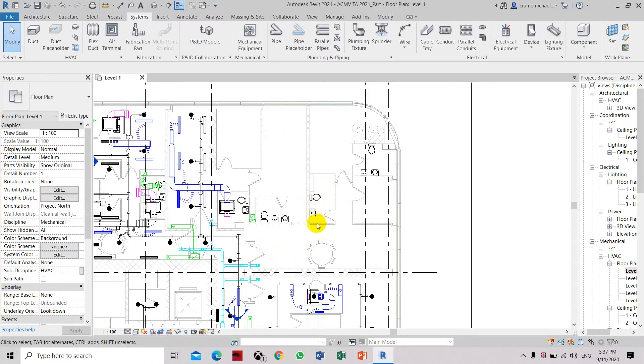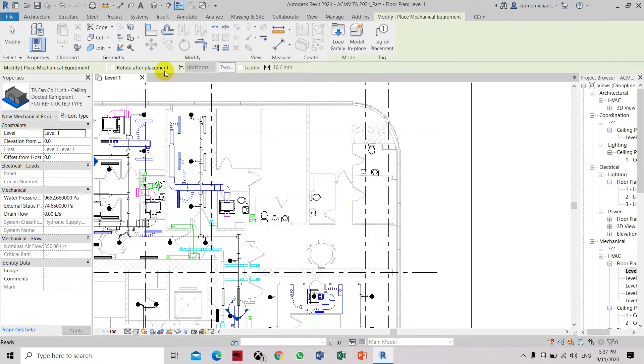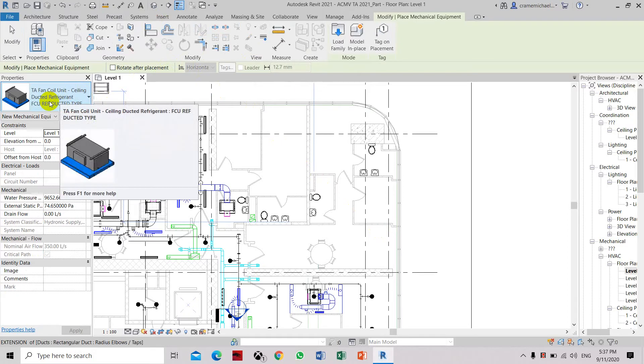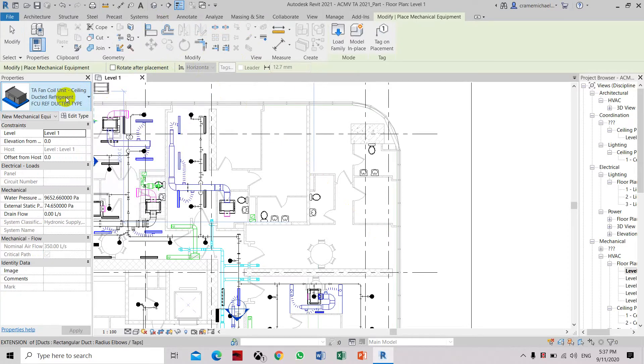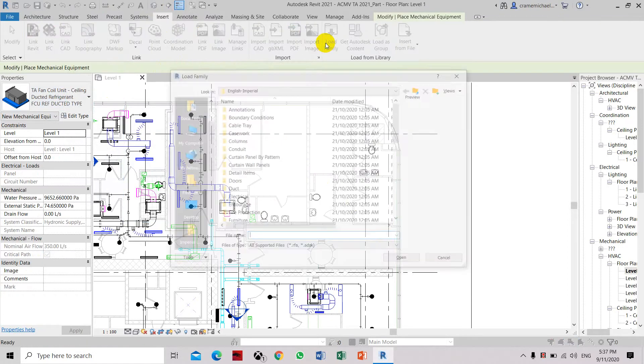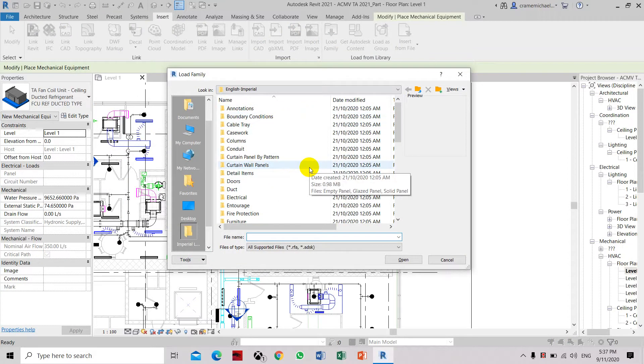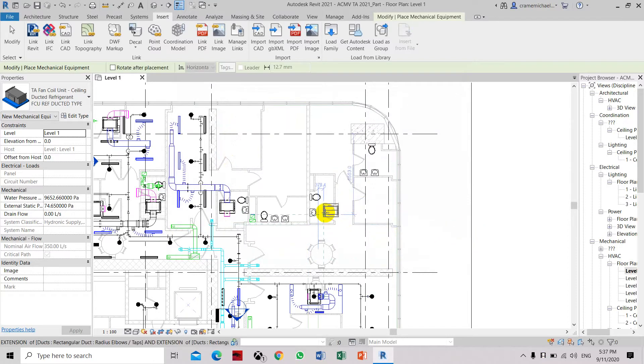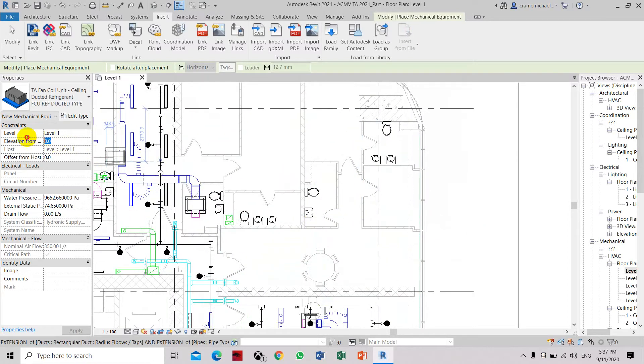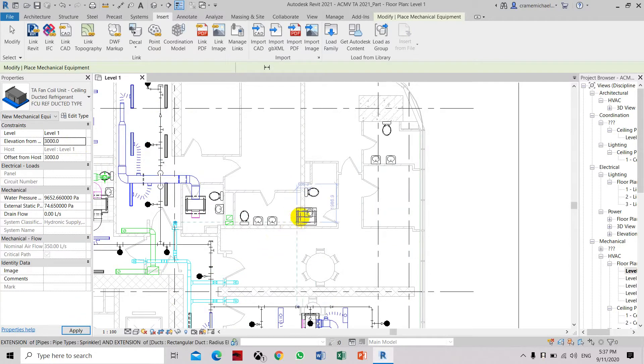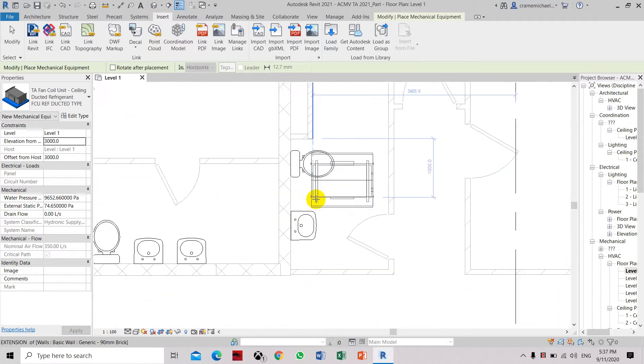We will now write the layout for the supply air grills in the living room. Go to System, Mechanical Equipment. I have already preloaded the fan coil unit family. If you haven't loaded your family, you can go to Insert, Load Family, and go to the relevant project or folder location. We have to set the elevation of the fan coil unit in respect to floor level, which is Level 1. Set it to 3 meters, click Apply, and click on the location for the fan coil unit.